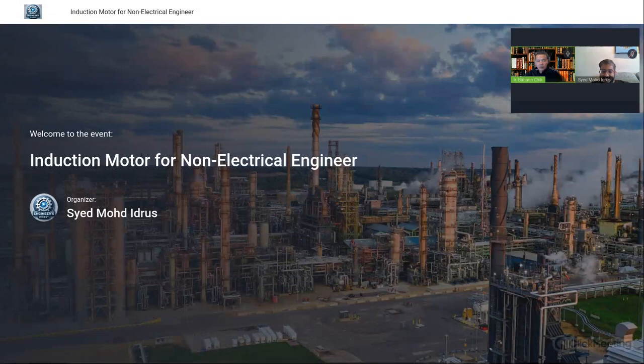Okay, so we understand now how to do the connection in Delta. So we saw also the 4-pole motor. How is the 4-pole motor generated using the same phase? We turn the winding in the opposite direction. Then you can have a pole. So this is the formula that we discussed just now on the RPM side. This is the synchronous machine.